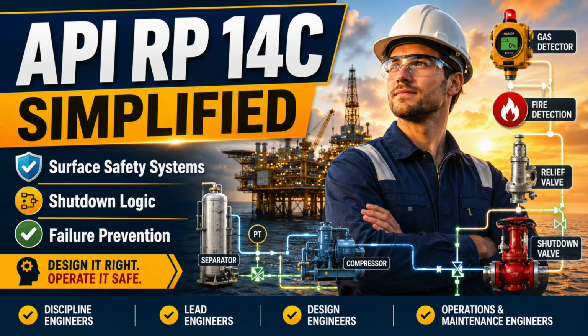A heat exchanger can experience external blockage, thermal expansion, tube rupture, and cross pressure from the high pressure side to the low pressure side. A fired heater adds flame failure, excess fuel, low combustion air, low process flow, high stack temperature, and uncontrolled ignition sources.